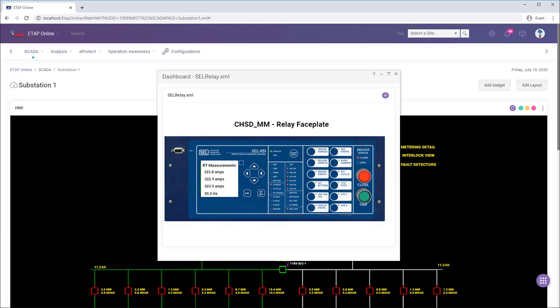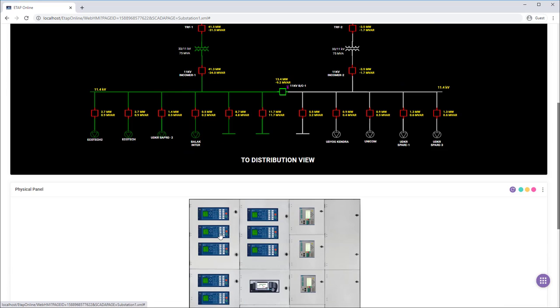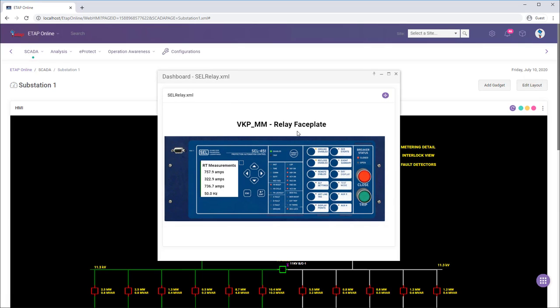Then you just select the template per relay, and the real-time data and all indicators from that relay are based off the specific relay model. So in this case, we're looking at CHSD_MM. All the data correlates to that relay specifically, but if I go to VKP_MM, now the real-time measurements are specific to this relay.